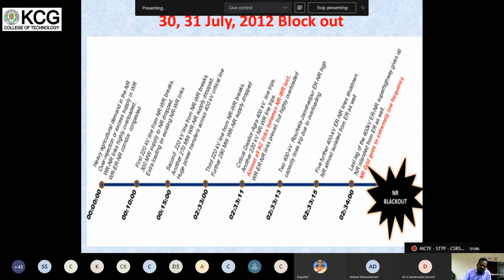Then at 1210, what happens? The first 220 kV line from NR to WR, the northern region, breaks. The 300 megawatt supply to the northern region dropped. Already it was drawing 5600 megawatt. Now 300 megawatt is out. Now after 5 minutes, what happened? The second 220 kV line from the northern region to the western region breaks. So another 270 megawatt supply from WR to NR, western region to northern region, dropped. The huge power transfer occurs on the 400 kV critical line. That means now overdrawal occurred. Now the northern region is drawing excess power through this 400 kV line.